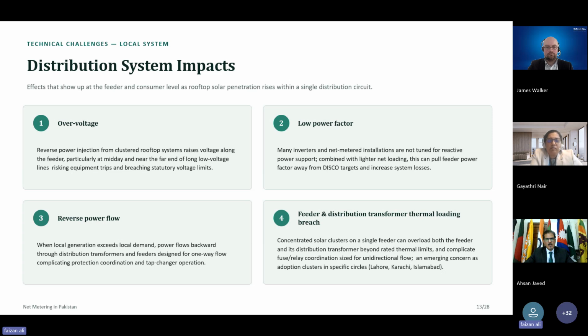And obviously, the reverse power flow is power as well, right? It is power. So your whole distribution system needs to be designed according to the reverse power flow, that is, how much power is now being supplied from the consumers towards the generation side. And then your protection systems need to change, your tap changer positions need to change. So all these settings need to be done as well.